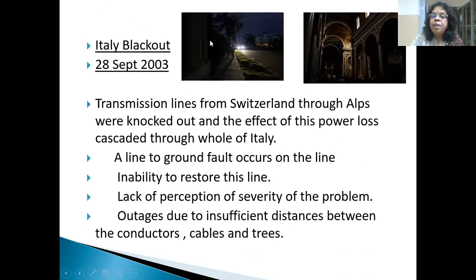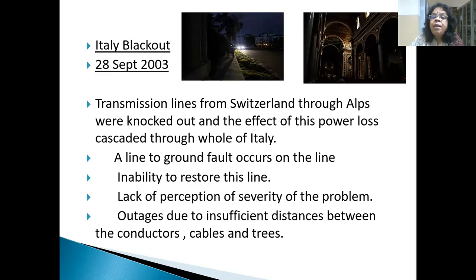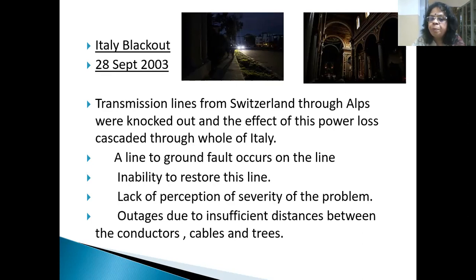Again in the same year, in September, there was a major blackout in Italy. Transmission lines from Switzerland through the Alps were knocked out, causing a cascading effect and power loss across almost entire Italy. A single line-to-ground fault occurred and the line was not restored. This led to cascaded outages because of insufficient distance between conductors and trees. Once again, we are back to the same issue — trees touching the conductors. Something as simple as cutting the trees could have prevented it.